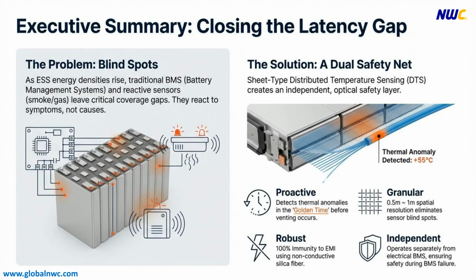NWC's sheet-type DTS addresses this issue by using non-conductive fiber optics, enabling ultra-precise temperature monitoring with 0.5 meter spatial resolution, completely free from electromagnetic interference. This system detects abnormal thermal signatures during the golden time before gas venting occurs, allowing potential hazards to be identified at the earliest stage. By introducing an independent optical safety layer, NWC's technology overcomes the limitations of existing systems and establishes a new dual-layered defense architecture for ESS safety.